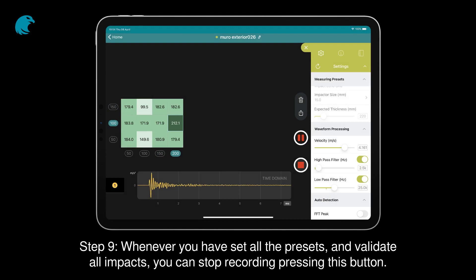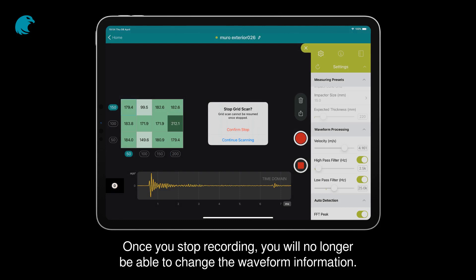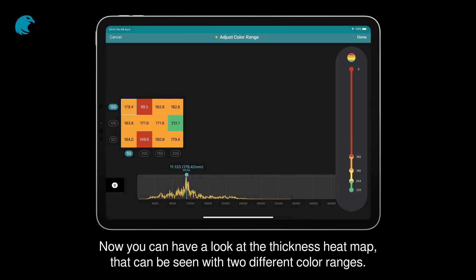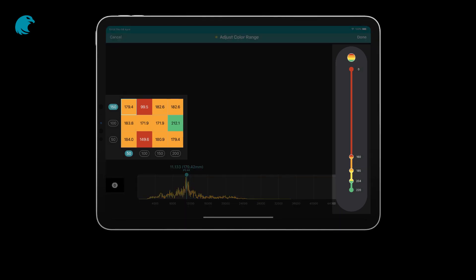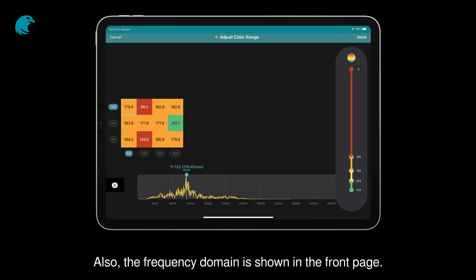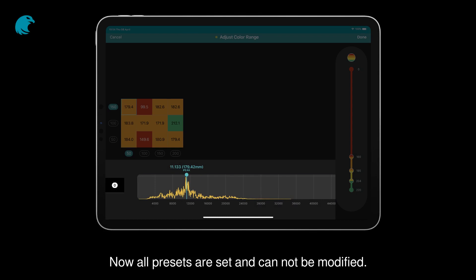Step 9. Whenever you have set all the presets and validated all impacts, you can stop recording by pressing this button. Once you stop recording, you will no longer be able to change the waveform information. Now you can have a look at the thickness heat map, which can be seen with two different color ranges. Also, the frequency domain is shown on the front page. Now all presets are set and cannot be modified.